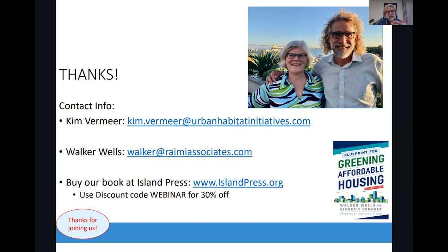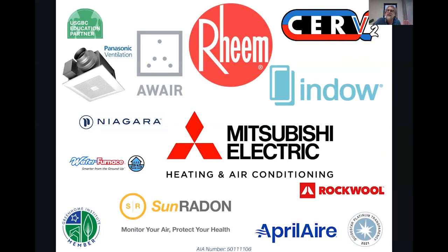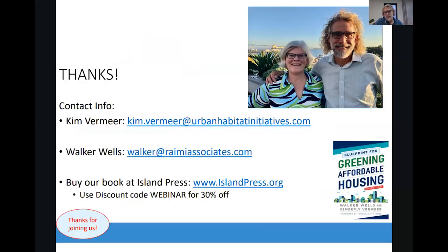So again, at least in the affordable housing projects, I'm always leery of pushing hard on innovative technology. I can remember my last gas boiler project, in which another very assertive energy consultant had cajoled these developers into saying, you have to do all electric. It's an abomination to do natural gas in 2018. And I told them, look, the gas is right there at your building. You're burning it at 96% efficiency. We're offsetting 70% of the energy needs with solar thermal, and the grid is only 20% renewables. So no, do the gas.